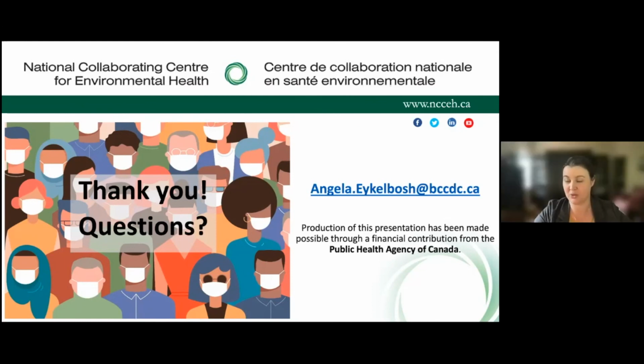This is something to start talking about within your health authority - how do we use these CO2 sensors reasonably and intelligently? Some handheld CO2 sensors aren't actually the type of monitor you'd put on a wall; they're safety devices meant to monitor at a much higher set point, around 5,000 ppm, since the occupational exposure limit for CO2 is 5,000 ppm over an 8-hour shift. Those handheld devices are usually meant for figuring out whether a worker is safe or not. So if you're walking around with one trying to guesstimate whether a patio is close to ambient, I'm not sure that device will do what you want.